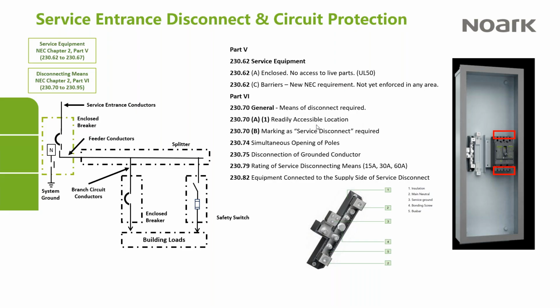Part 6 is fairly general. It says a means of disconnect is required. It has to be in a readily accessible location, and it has to be marked as a service disconnect. And you'll see in the packaging for our product, we supply a label that says it's suitable as a service disconnect. Other really basic things, all of the poles of the disconnect must open together. And then there's this talk about the disconnection of the grounded conductor. So this is the bonding means that I talked about.